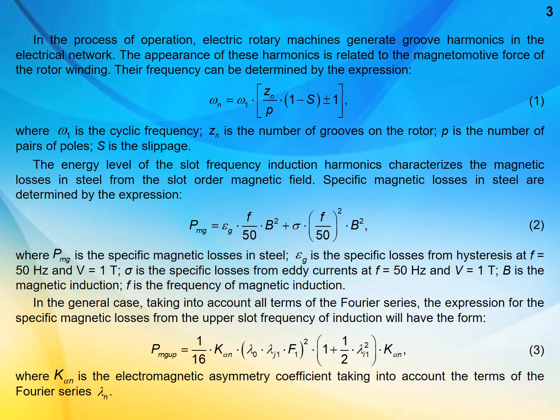In the process of operation, electric rotary machines generate groove harmonics in the electrical network. The appearance of these harmonics is related to the magnetomotive force of the rotor winding. Their frequency can be determined by expression 1. The amplitude value of these harmonics is determined by the design parameters of the electric machine and the network voltage. The significant danger of groove harmonics is caused by the dependence of these frequencies on the network frequency and slip, which can lead to resonance phenomena.